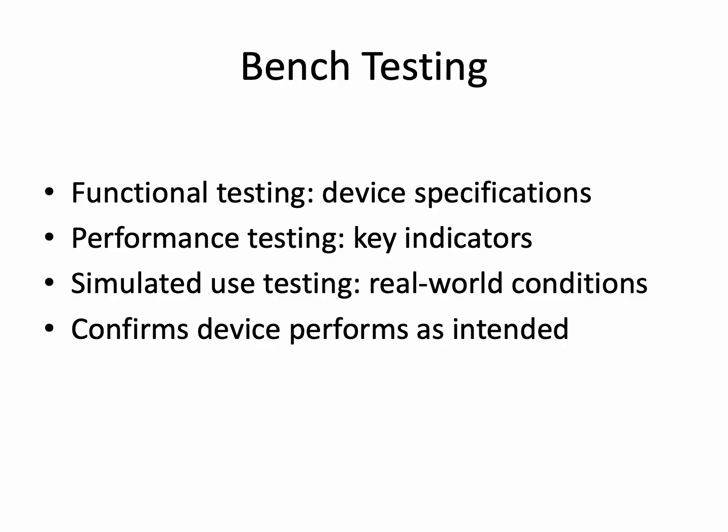Bench testing is conducted in a laboratory to confirm that the device meets design and functional specifications. Functional testing ensures that the device operates according to intended use. Performance testing measures critical performance indicators, and simulated use testing recreates real-world conditions. Bench testing provides essential preclinical evidence of safety and efficacy, supporting regulatory submissions and informing subsequent preclinical and clinical studies.